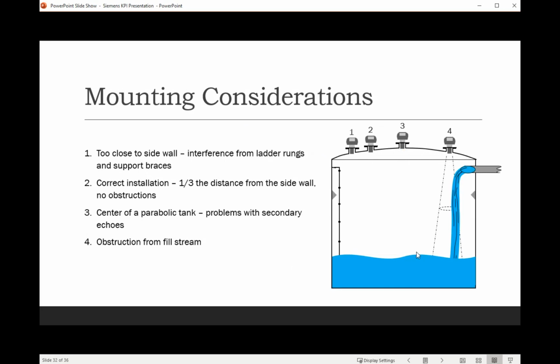And then for mounting consideration number 4, when there's no flow coming into the tank, you'll probably have a good reading, probably have a solid signal back, but as soon as you have water coming in, you're going to lose signal and they have a high reading.